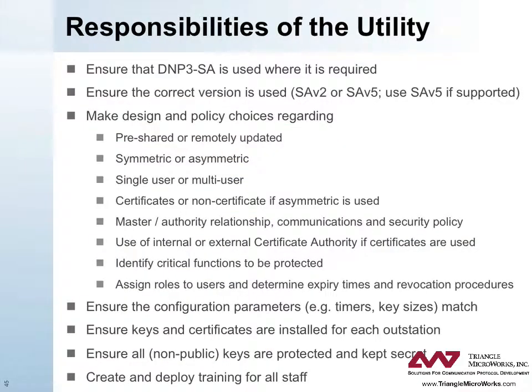Finally, let's look at some of the responsibilities of the utility. These include ensuring that DNP3 secure authentication is used where required and ensuring the correct version is used — that is, SA-V2 or SA-V5. They should use SA-V5 if it's supported. The utility is also responsible for making design and policy choices regarding whether to use pre-shared or remotely updated keys, whether to use symmetric or asymmetric, and if asymmetric, whether to use certificates or non-certificates, and whether to use single-user or multi-user mode. If a certificate is used, the utility is responsible for determining whether to use an internal or external certificate authority. In addition, the utility is responsible for establishing a master-authority relationship, communications and security policy, identifying critical functions to be protected, and assigning roles to users and determining expiry times and revocation procedures. The utility is also responsible for ensuring configuration parameters such as timers and key sizes match, ensuring keys and certificates are installed for each outstation, ensuring all non-public keys are protected and kept secret, and for creating and deploying training for all staff.